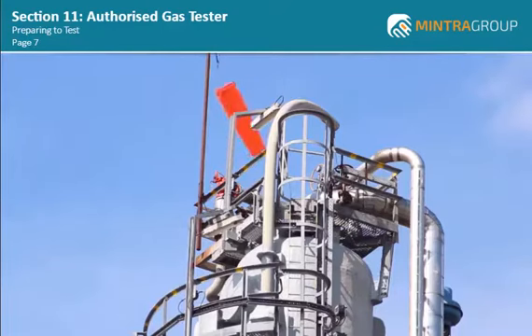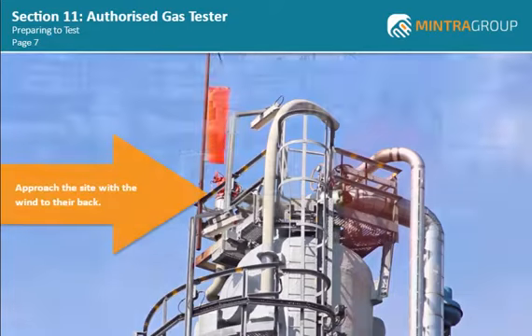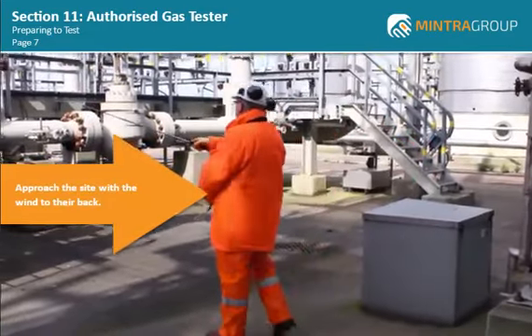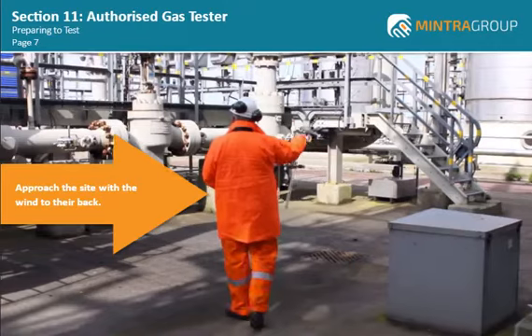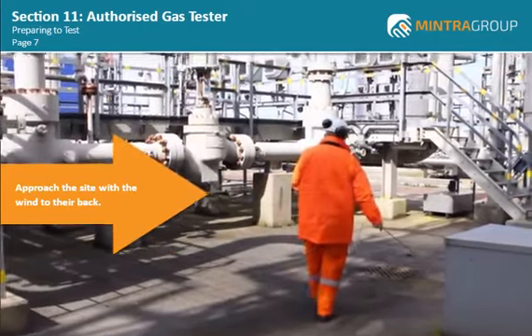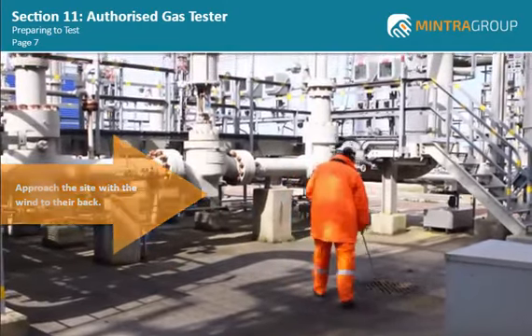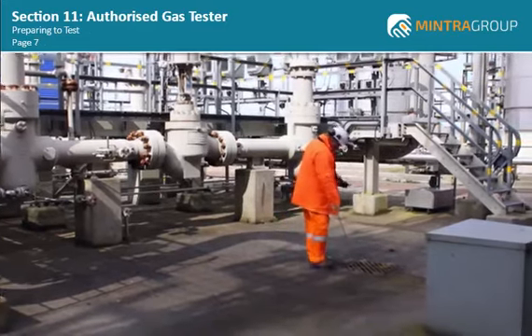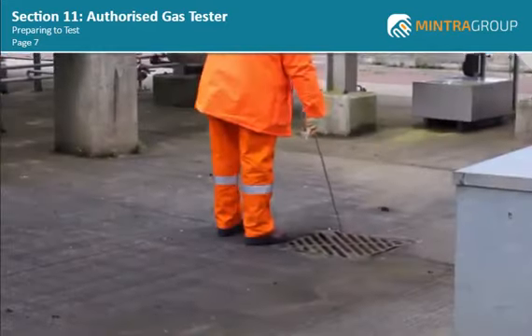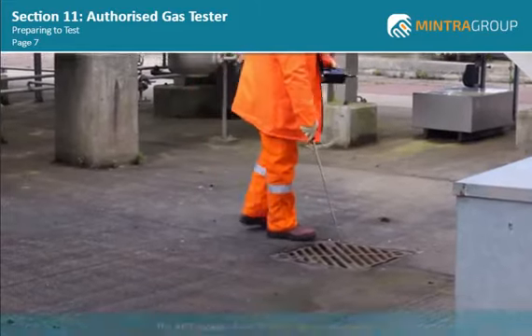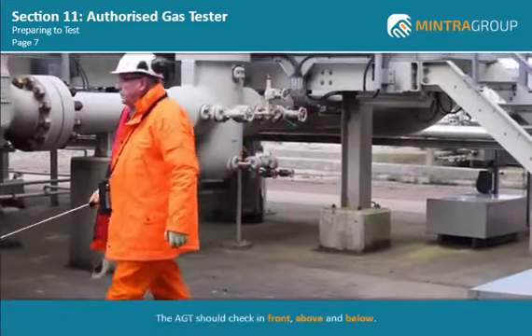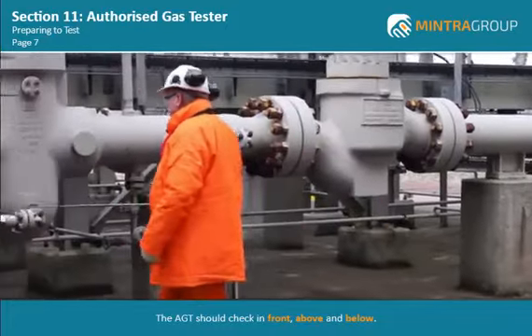Before moving towards the test area, the AGT will check the wind direction. They will then approach the site with the wind to their back to ensure that they're not walking into a toxic gas cloud. The wind will be driving any gases away from the AGT. As a potential gas leak is unknown, the AGT must check the atmosphere all around them as they approach the site. Remember, the AGT should check in front, above and below.